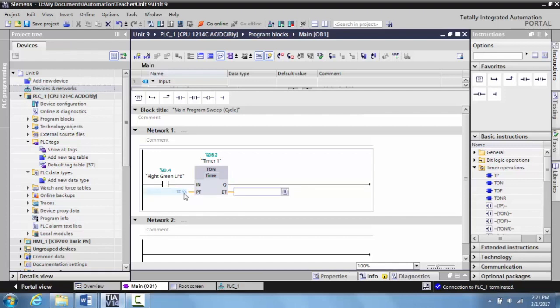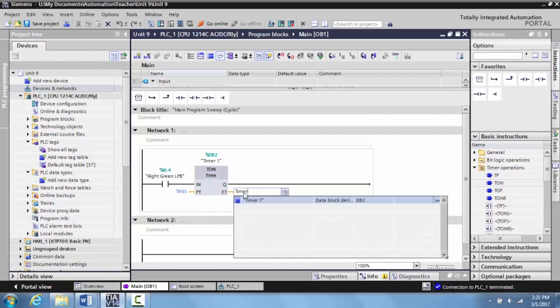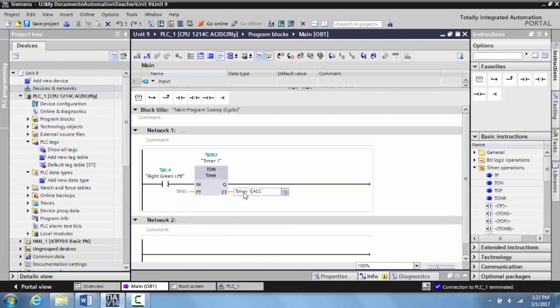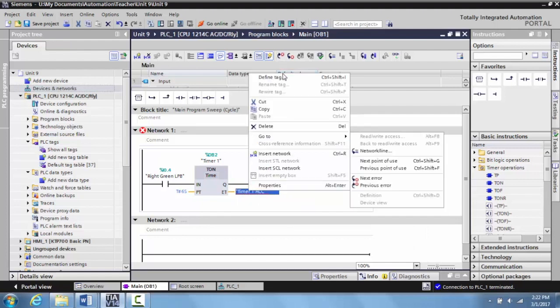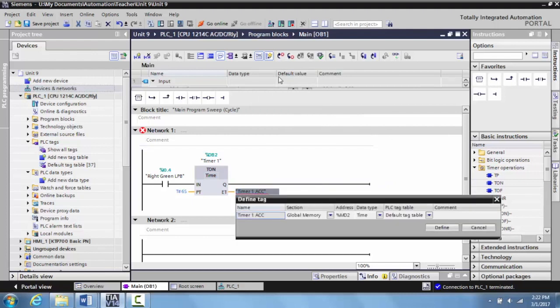Your ET is going to be the amount of time that is actually accumulated. If you're coming from the Allen Bradley world, this is your accumulated value. We're going to type in a tag here: timer one acc. That's timer one's accumulated value. Hit enter and then you're going to define this, so left click define tag.